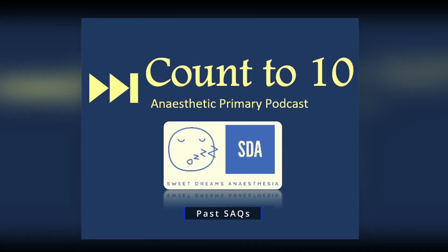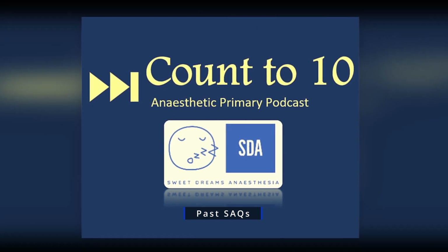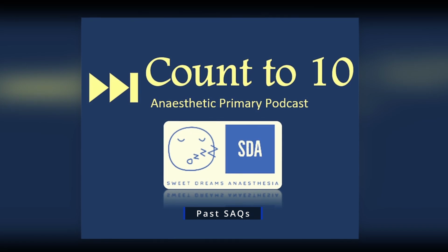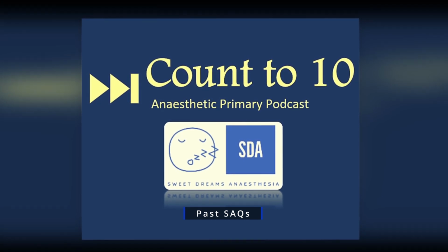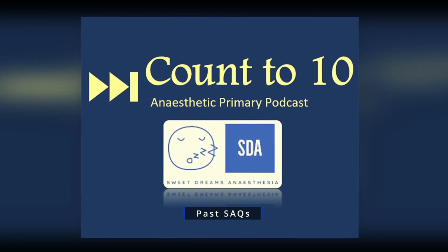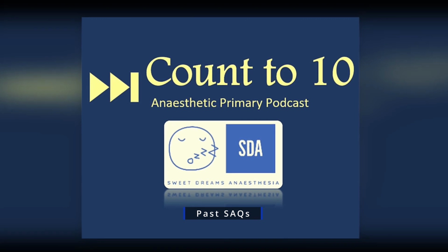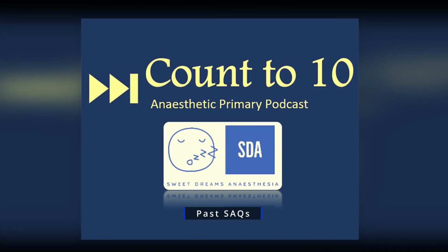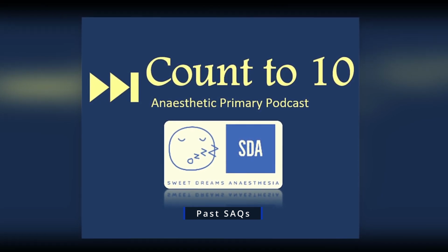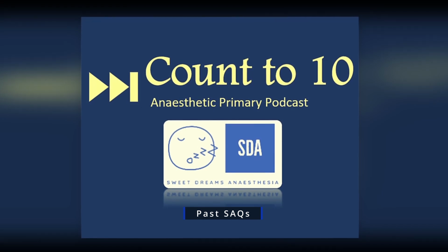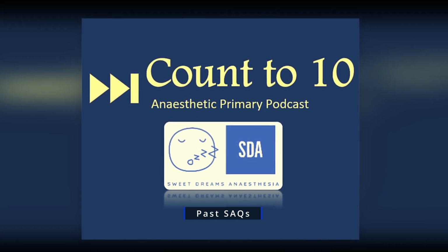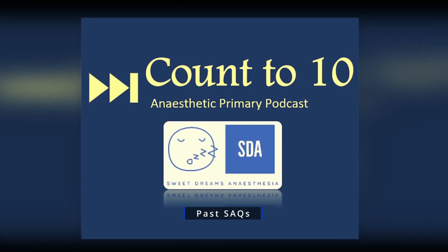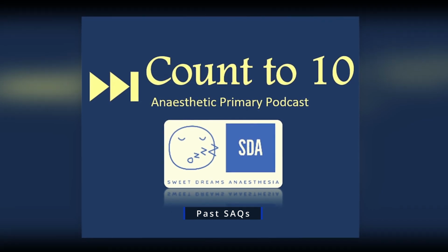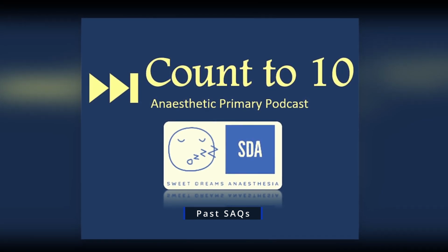Within dynamic errors, you have resonance, which is the increase in amplitude of the wave as it approaches its natural frequency. And here I would have a clear definition of natural frequency, which is a tendency of a system to remain in oscillations once an energy is applied. The other key thing to put in here is that the natural frequency of the arterial system is 200 Hz. It's well above the natural frequency of arterial pulsations, which is 3 Hz at its maximum.